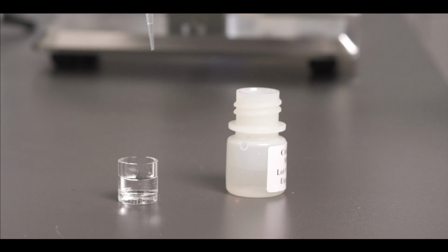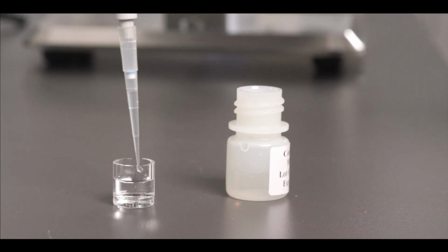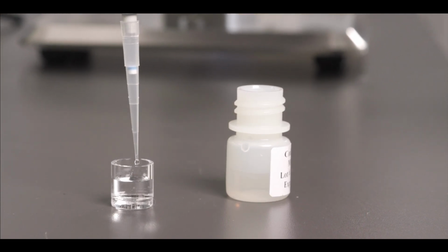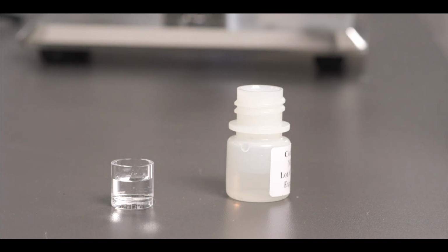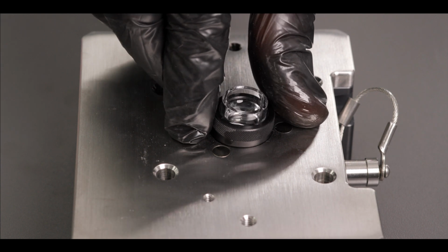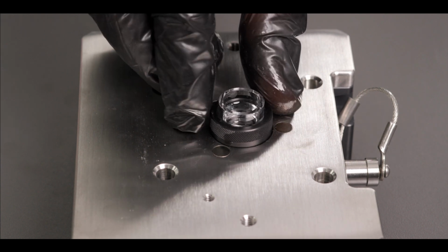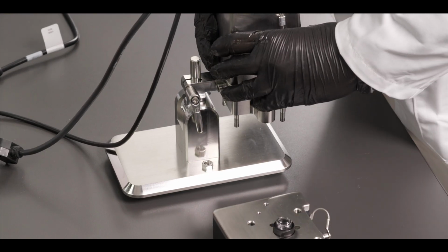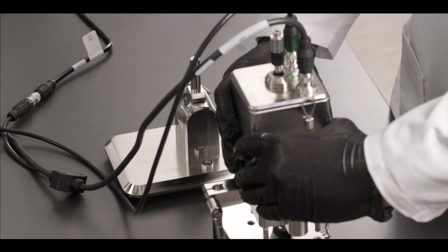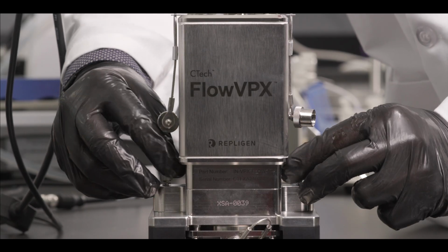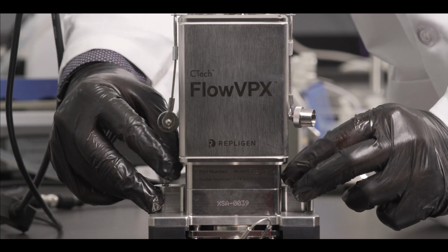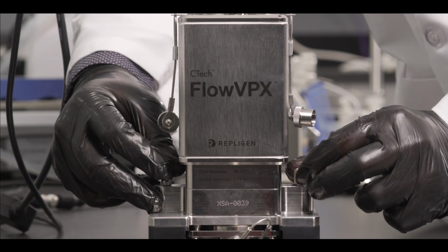Either use a new sample vessel or thoroughly clean the used sample vessel before inserting the new sample into the vessel. For proper cleaning of the sample vessels, refer to our video on the subject. Load the sample vessel into the DVA unit. Place the FlowVPX head and XSA assembly into the DVA. Screw and tighten the XSA unit to the DVA unit using the two spring-loaded screws.